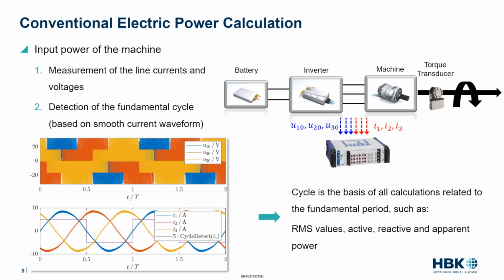And we have here the inverter output voltages. And of course, due to the functionality of an inverter, these inverter output voltages contain the high frequency content, which is related to the inverter switching. So the steep switching edges an inverter typically produces during operation. And therefore, the inverter output voltages are disturbed with this high frequency content, by functional principle. But since the electric machine typically represents a highly inductive load, the machine currents are much smoother. Of course, if you zoom in here, you could also see some high frequency content in the currents, but the currents are much smoother compared to the voltage in a lot of typical applications.